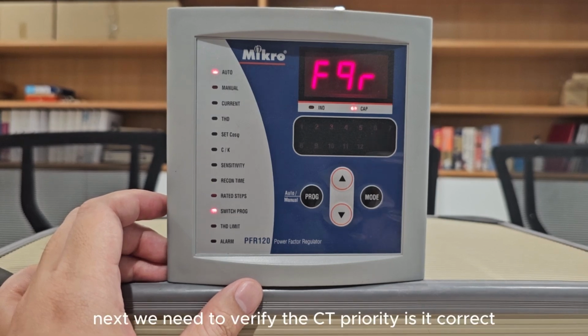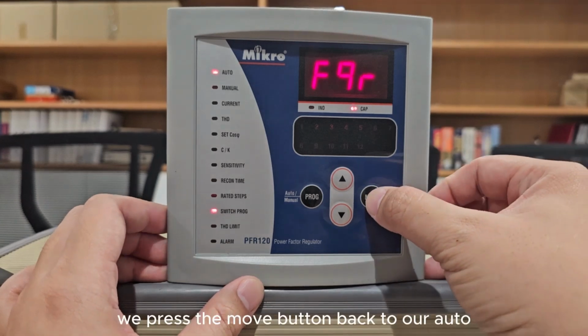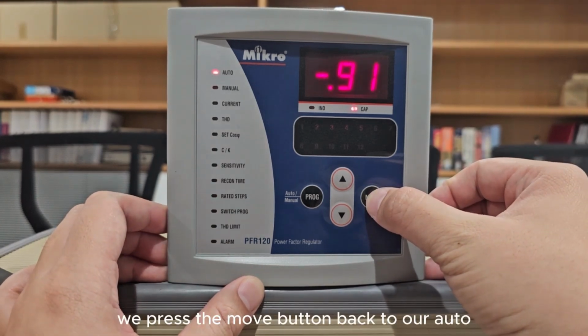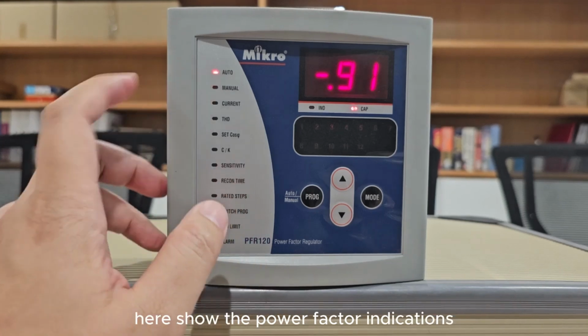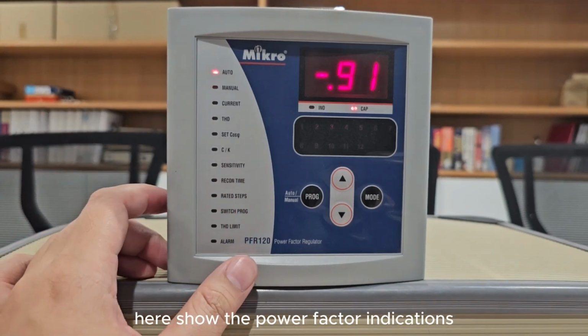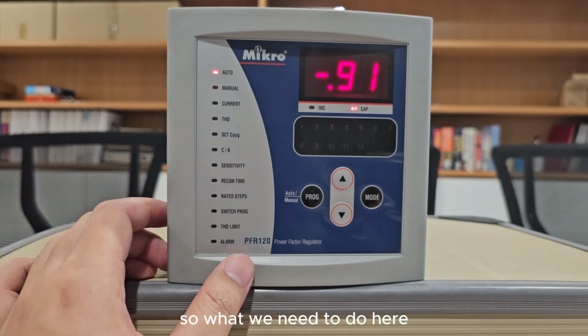Okay, next we need to verify the CT polarity. Is it correct? We press the mode button. Back to our automatic here, it shows the power factor indications. So what we need to do here, we need to turn off the solar energy generation in this case to ensure that it's only import power in the grid.